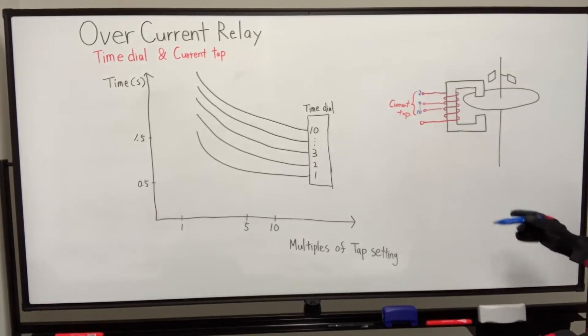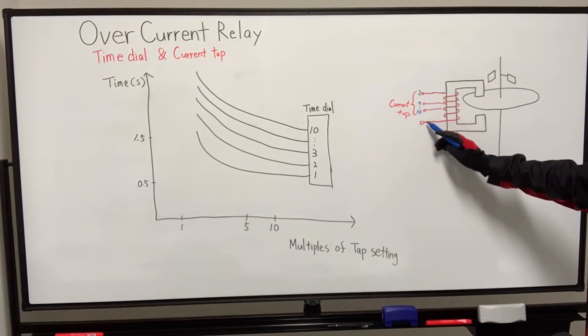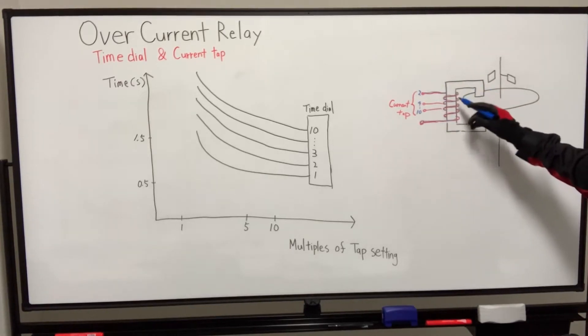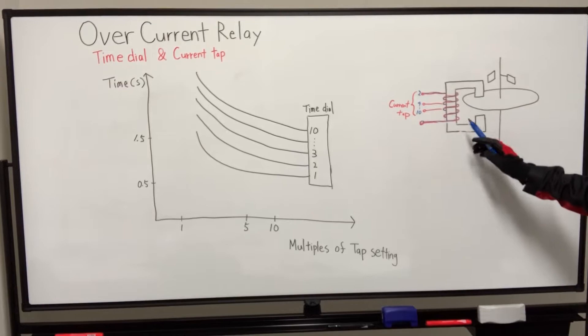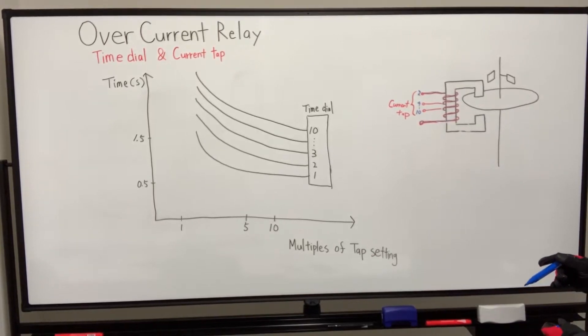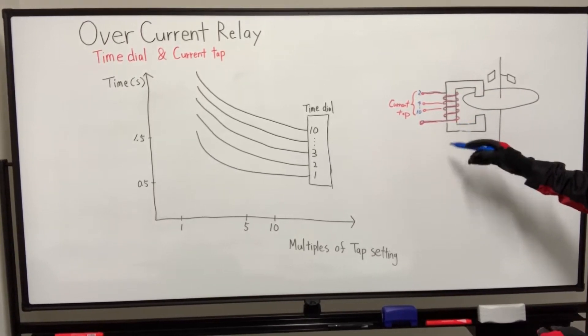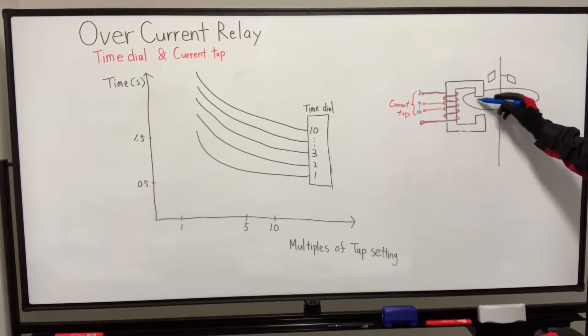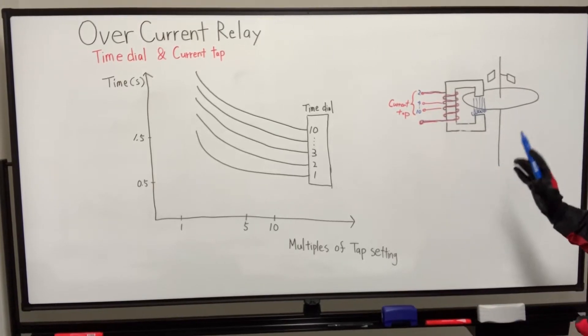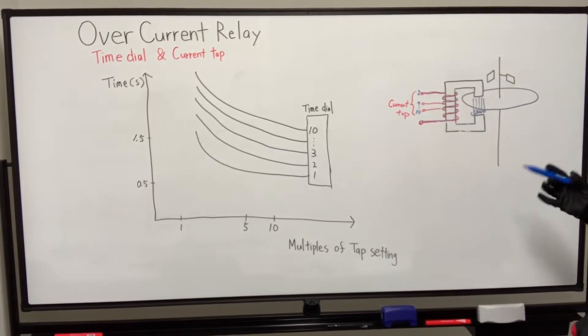So if a current tap is set to number 2, the fixed contact is here, and number 2 is from here. The coil which is energized by fault current is relatively long. So the longer coil creates a stronger magnetic field. That means the disk rotates powerfully, and the contact will close quickly.